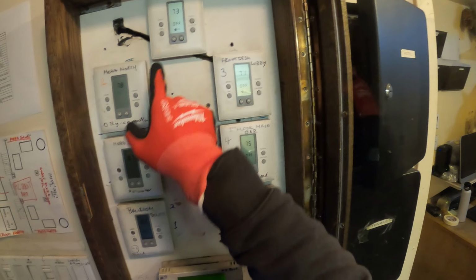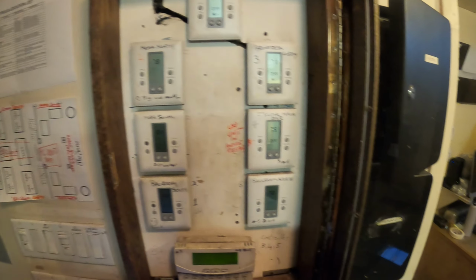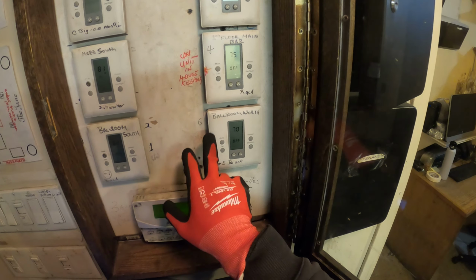All right, so this is the vestibule, front desk lobby. Can't be it. Mess south, mess north, no. Ballroom north, ballroom south. So it's either between 1, 2, or 3. So I set those to cool, and typically I do that because you're just more comfortable and aware with those cooling pressures. And wow, this place is so cool. So let's make our way back up there and see what happens.